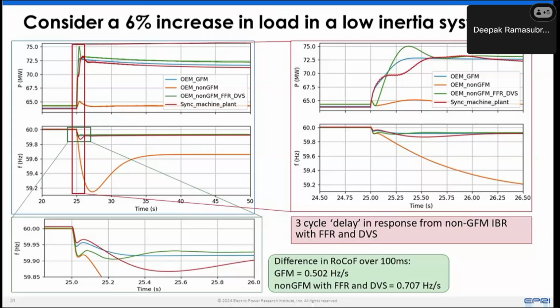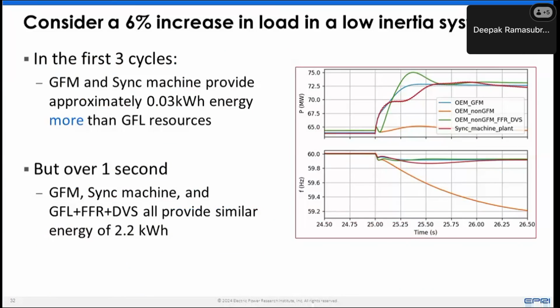So what does all of this have to do with the frequency response of an interconnection with a varying percentage of inverter-based resources? It comes down to energy. It comes down to how much energy one wants to inject and at what point in time that energy should be injected. If you look at the next slide, we can break this up to understand the energy injection. Just looking at the instant of the disturbance, in the first 3 cycles after the disturbance occurs, a synchronous machine and a grid forming resource in this particular configuration and system provide around 0.03 kilowatt hours more energy injection than a non-grid forming resource would. But that's only in those first 3 cycles. If you look at the entire 1 second of response, they all provide a similar amount of energy.